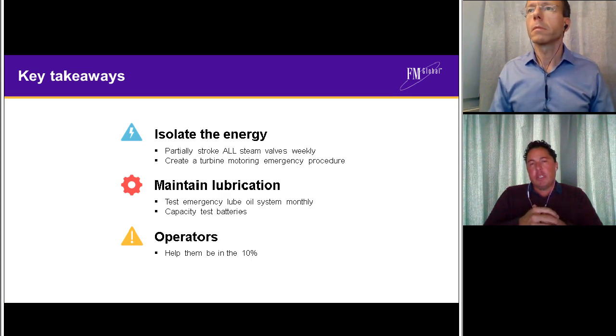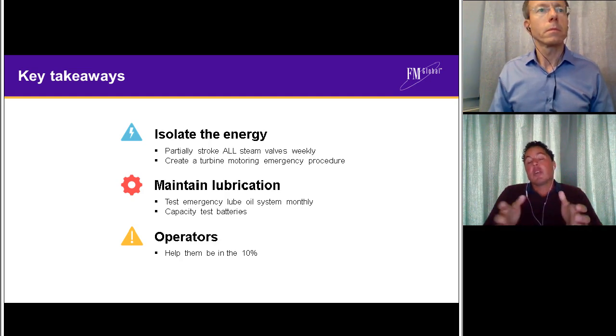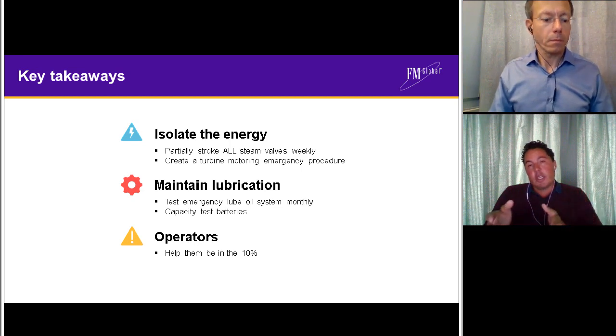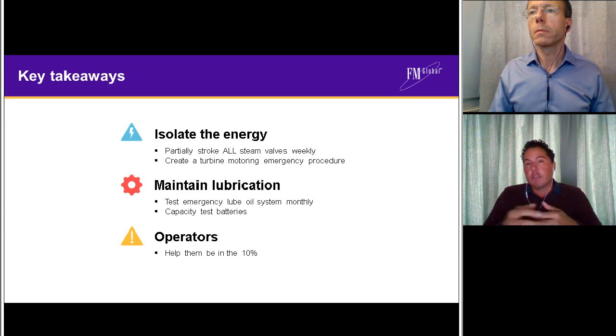One of my pet subjects is the batteries that supply those DC systems and the technology selection. I think for some fairly understandable reasons, valve-regulated lead-acid batteries have become incredibly popular, not least of which is that at the purchase point, they are significantly cheaper than competing technologies. But as I alluded to earlier, their sensitivities are starting to be better and better understood: their sensitivity to environmental factors, their sensitivity to overcharging and ripple currents, and their life, even if they're looked after, is a fair bit shorter.